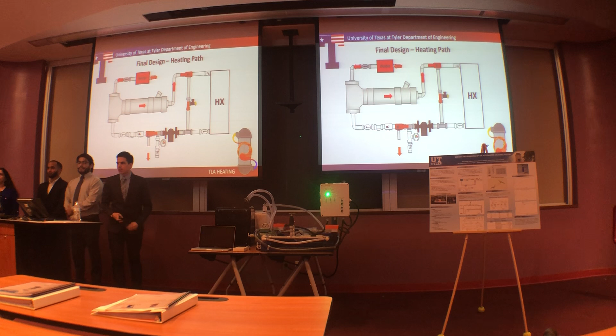Thank you. So, as you can see, there are a lot of electrical components in our system that come into play. Essentially, this is our control layout for the power on our electrical components. We have a main breaker box with two breakers, a 20 amp and a 15 amp breaker, that feed off 120 volts. The 20 amp breaker powers both the heater and the chiller, whereas the 15 amp breaker powers all the other auxiliary systems.